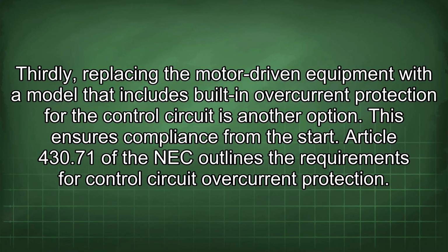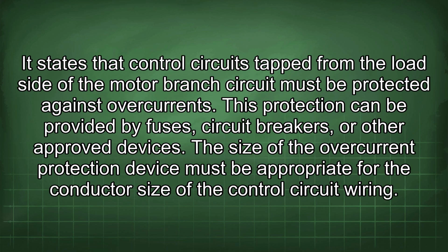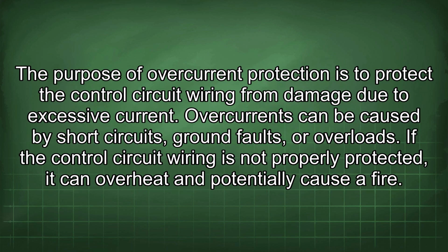Article 430.71 of the NEC outlines the requirements for control circuit overcurrent protection. It states that control circuits tapped from the load side of the motor branch circuit must be protected against overcurrents. This protection can be provided by fuses, circuit breakers, or other approved devices. The size of the overcurrent protection device must be appropriate for the conductor size of the control circuit wiring. The purpose of overcurrent protection is to protect the control circuit wiring from damage due to excessive current. Overcurrents can be caused by short circuits, ground faults, or overloads. If the control circuit wiring is not properly protected, it can overheat and potentially cause a fire.